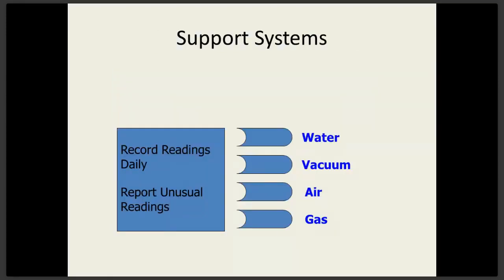Support systems include water, vacuum, air, and gases. And in your daily warm-up procedure, many times you're asked to take some basic readings on these just to make sure that the machine is in tip-top shape. As machines become more and more sophisticated, though, they're self-diagnostic and they will tell you when they are not happy, and they'll actually give you an error code that you can give to the service engineer who can probably tunnel in with a remote computer connection and even fix things remotely for you.